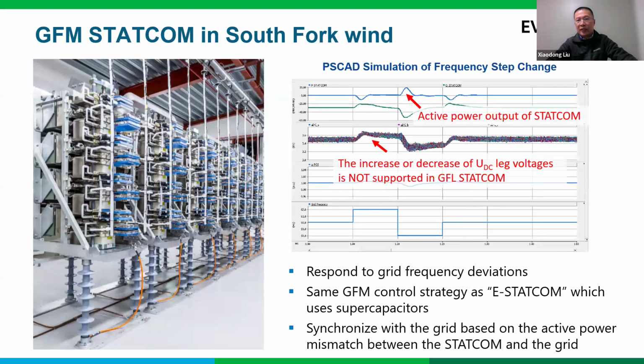This slide I want to show an example of a grid forming STATCOM responding to a frequency change. The capacitor cells in the STATCOM can discharge and absorb the energy and inject active power or absorb active power. And you can see the DC voltage, the DC link voltage, changes with the frequency change. This behavior is not observed in the grid following control strategy.